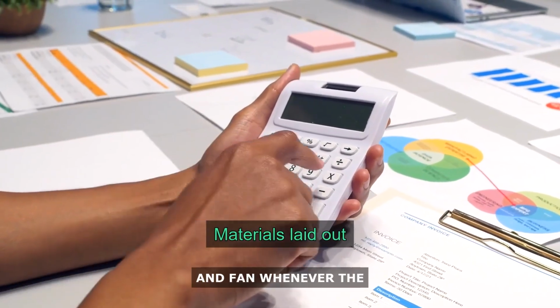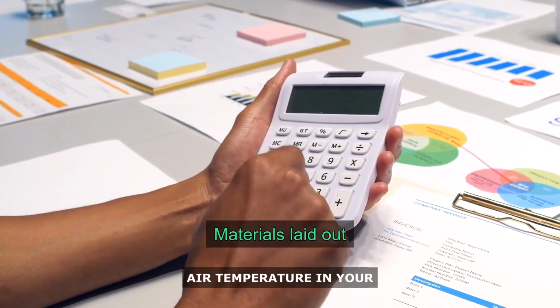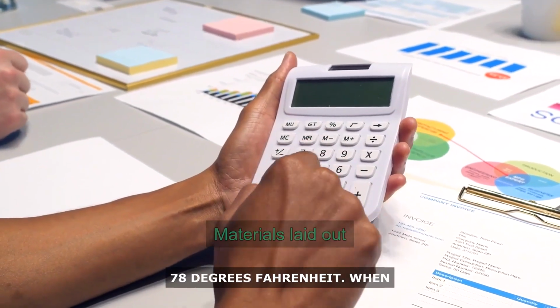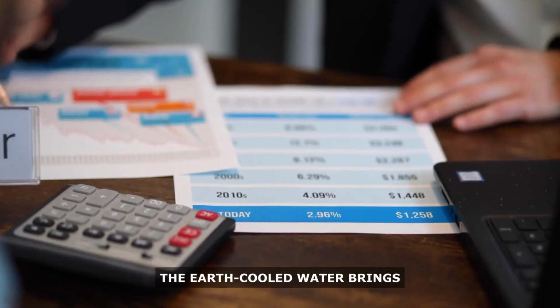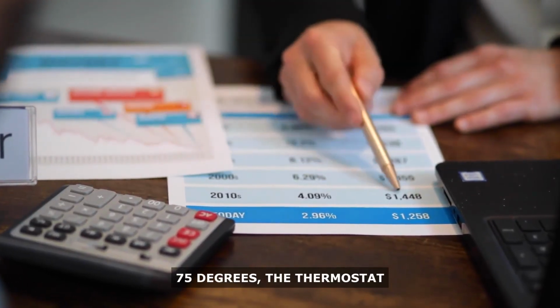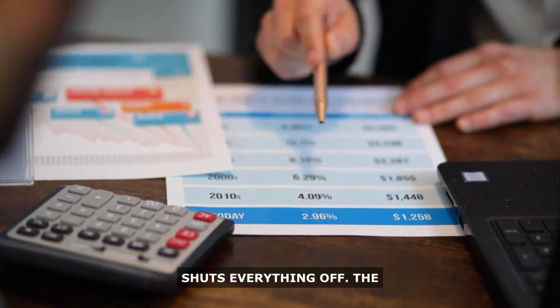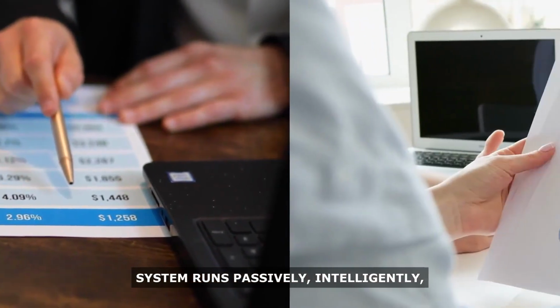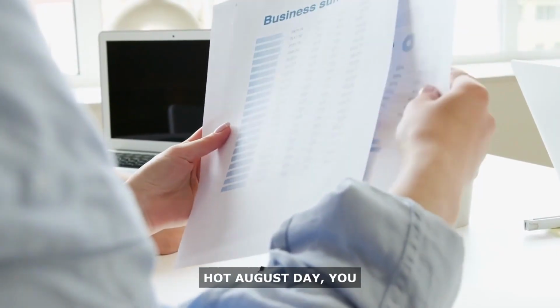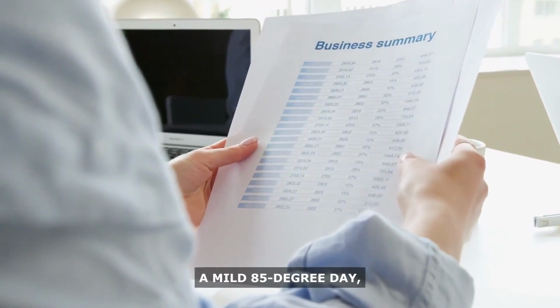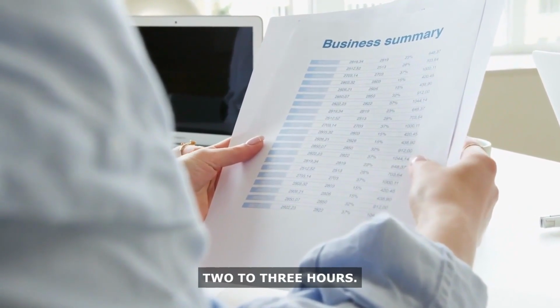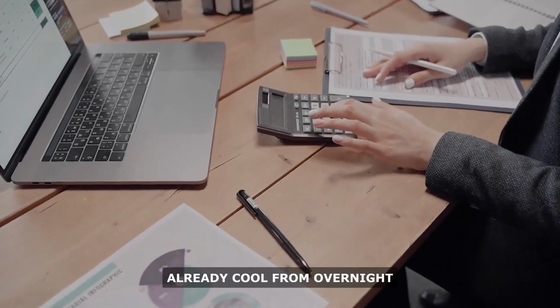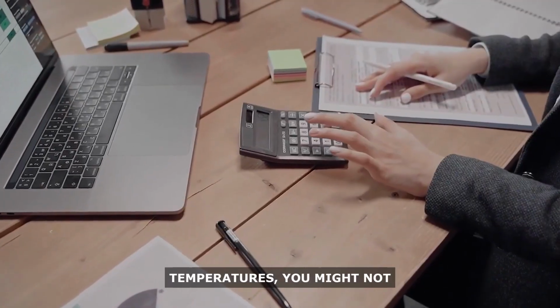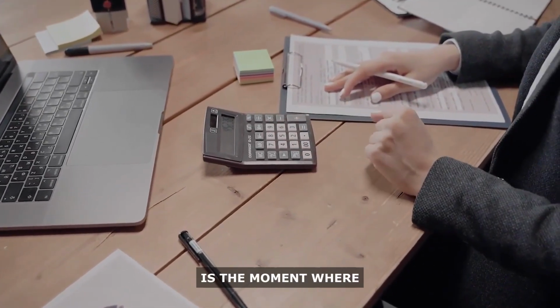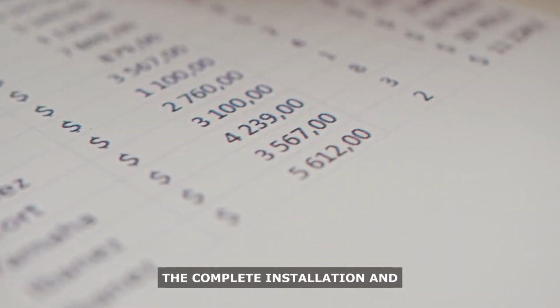The thermostat is the intelligence layer. You set it to turn on the pump and fan whenever the air temperature in your chosen room exceeds, say, 78 degrees Fahrenheit. When the earth-cooled water brings the temperature down to 75 degrees, the thermostat shuts everything off. The system runs passively, intelligently, and cheaply. On a hot August day, you might run for 6 to 8 hours. On a mild 85-degree day, you might run for 2 to 3 hours. On a day that's already cool from overnight temperatures, you might not run at all.